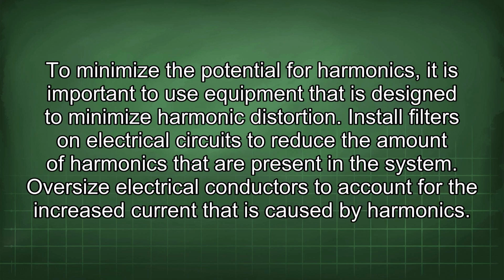To minimize the potential for harmonics, it is important to use equipment that is designed to minimize harmonic distortion. Install filters on electrical circuits to reduce the amount of harmonics that are present in the system. Oversize electrical conductors to account for the increased current that is caused by harmonics.